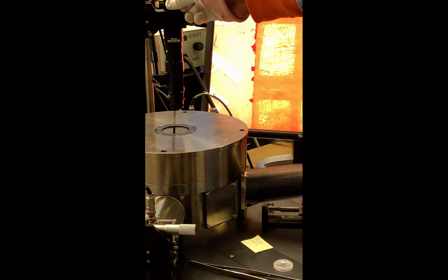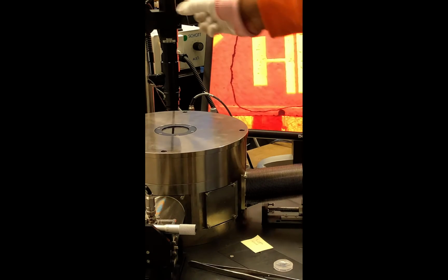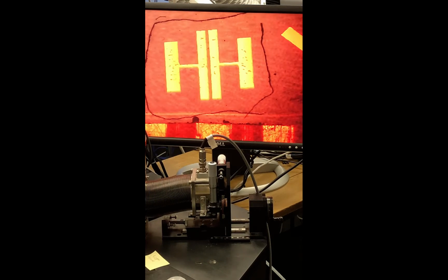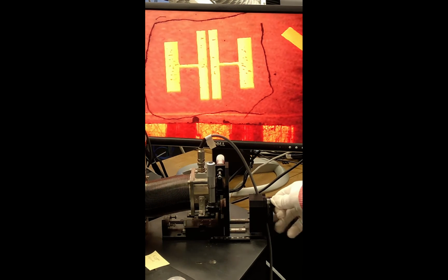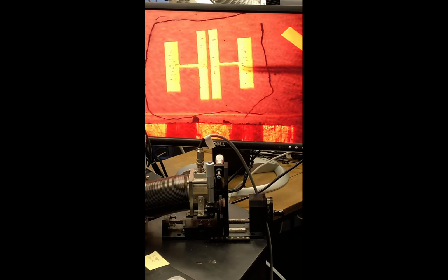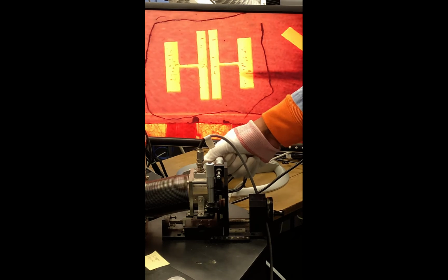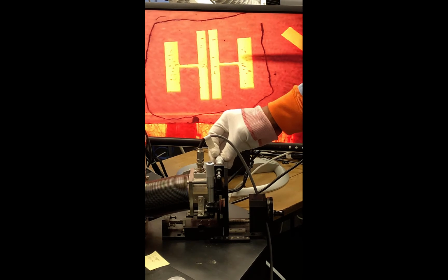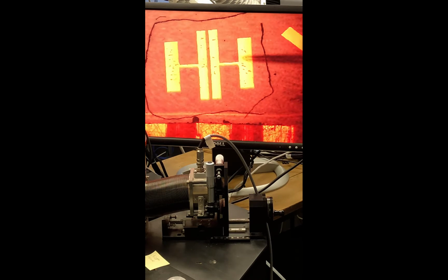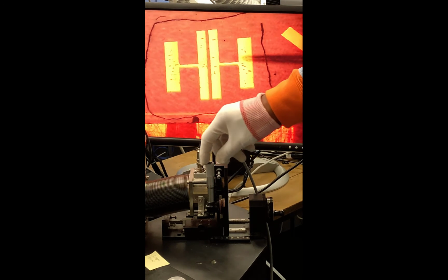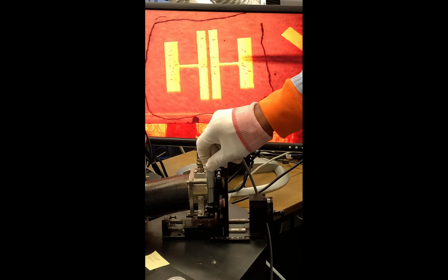Move the scope over the sample once again to help position the probe tips. There are 3 knobs used to move the probe tip in the 3 dimensions. The black one moves it forward and backward. There's a silver one pointed horizontally that moves it left and right, and there's another silver one pointed vertically that moves it up and down.